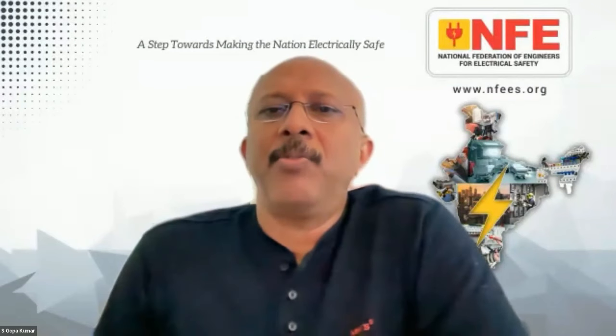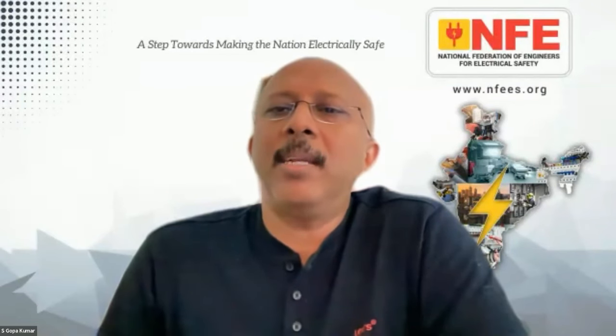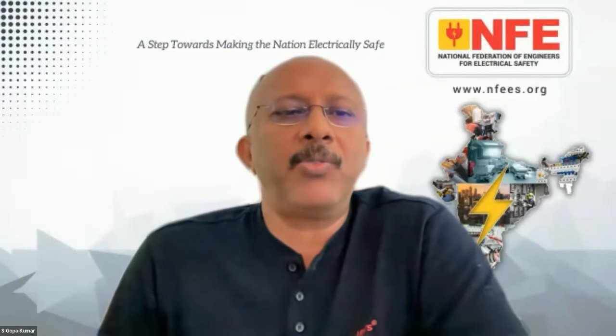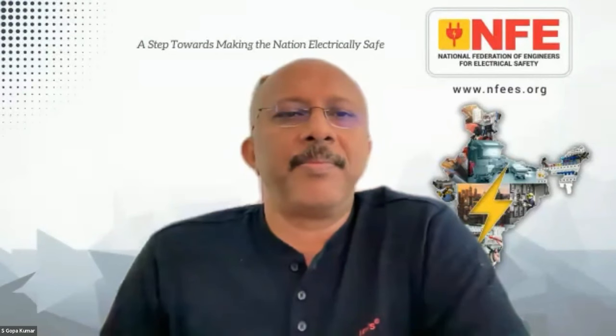Yeah. So thank you. Thanks for the answer. The next question is, is it recommended to install an RCD as a mitigation if the fault loop impedance test fails? That means as a measure for fault protection. Yes, it is. However, there is a folly of our industry. We have this very terrible rule of the 1,667 ohms. You can allow 1,667 ohms if you have an RCD. But that still doesn't offer you any protection against fault currents. It's only earth leakage. So if you have 1,500 ohms, yes, if you have earth leakage, you can rely on your RCD. But if you have an overcurrent, you've got nothing still.